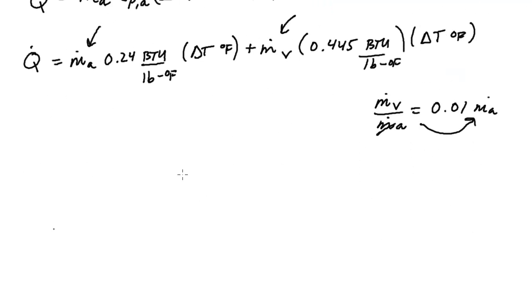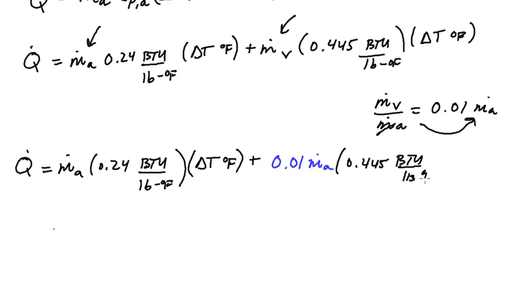So let me go ahead and rewrite that. We have Q dot is M dot A times 0.24 BTU per pound degree F multiplied by your delta T, your change in temperature multiplied. So this M dot V now got changed into 0.01 M dot A, and we're going to multiply that by our specific heat 0.445 BTU per pound degree F, poor handwriting, delta T, degree F.